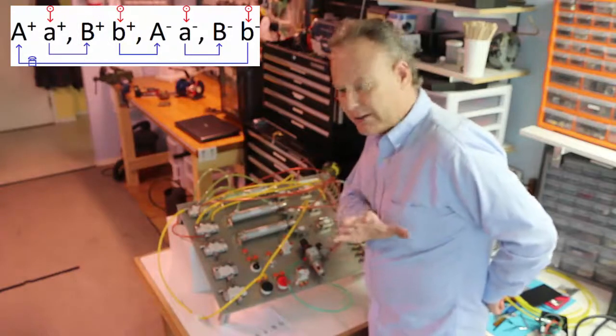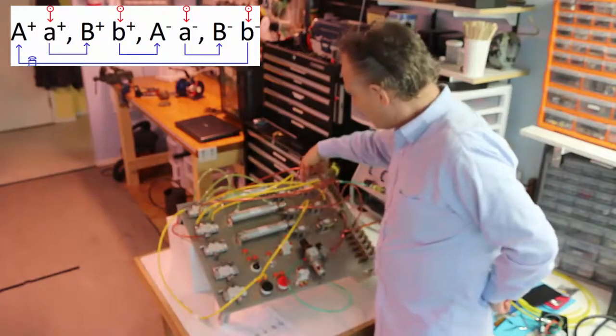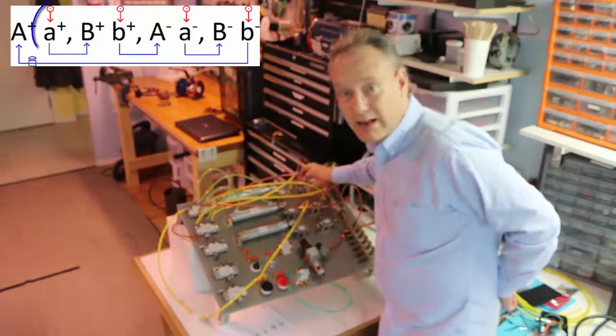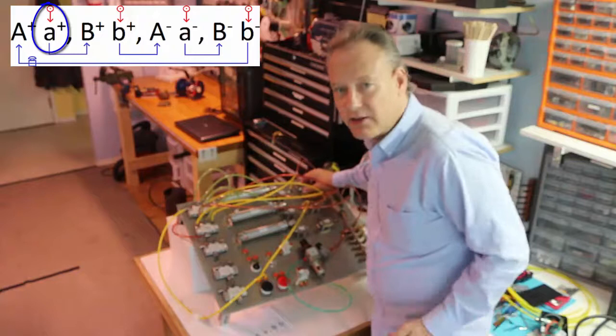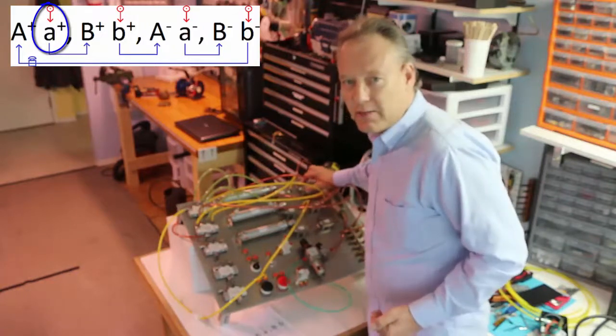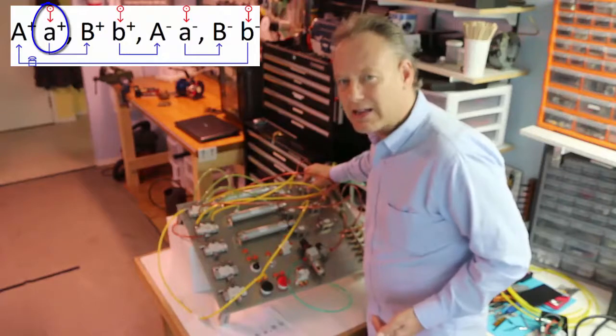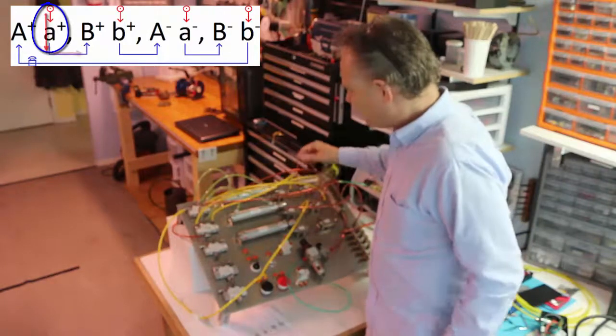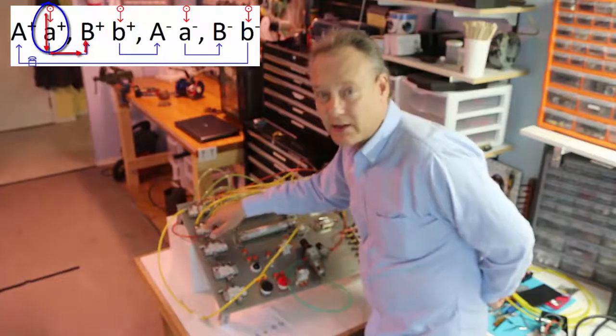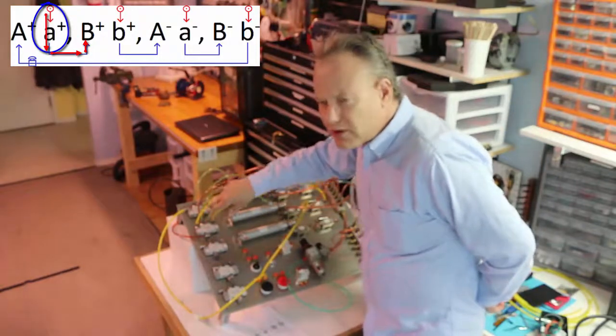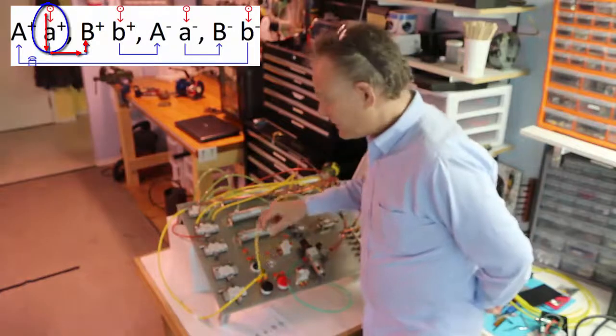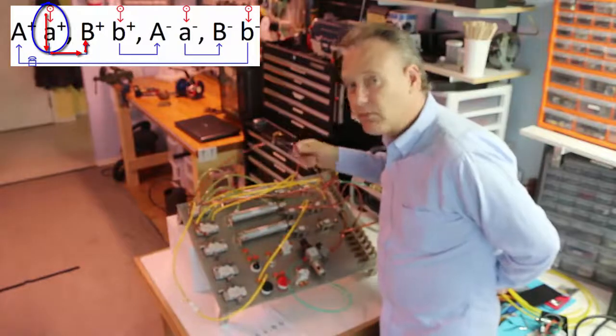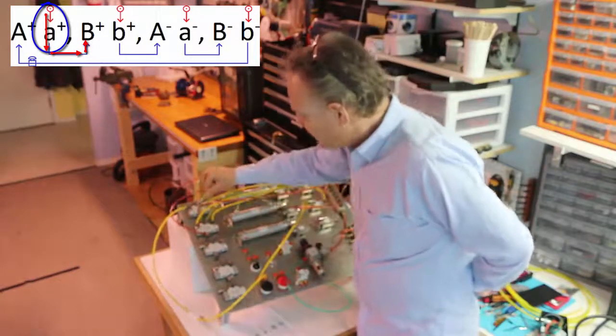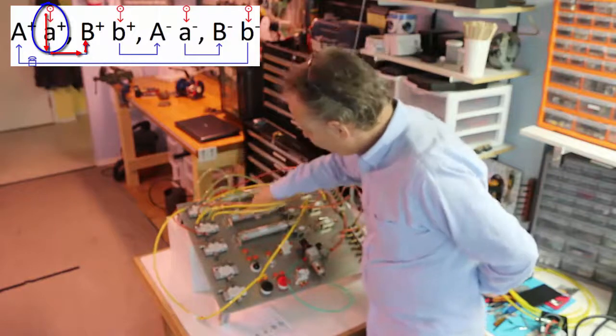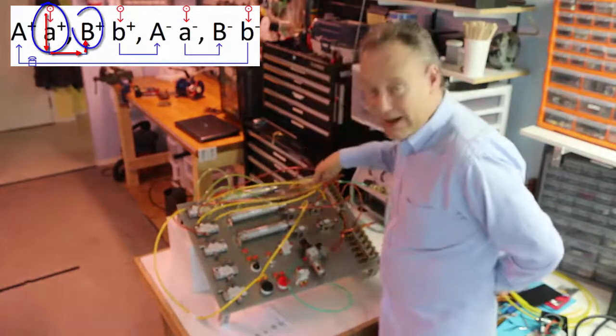Let me back up on that again. When this activates, it goes into its active state. It's a normally closed valve. It becomes open or passing. Now the air coming out of here goes into the pilot of this DCV. It moves the spool inside the DCV. That spool makes air coming from supply, nice red hose, come out this hose. So now the air is going to go into there and it's going to make this extend.